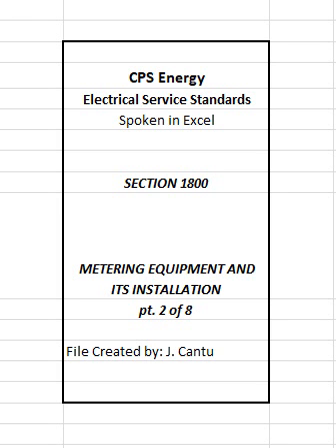Exception. Where customer's service design requires the use of a larger instrument transformer enclosure than those furnished by CPS Energy, customer shall submit to CPS Energy for approval an enclosure meeting CPS Energy's specifications and construction criteria. 2. Multiple meter installations. On multiple meter installations where CPS Energy instrument transformers are required in accordance with this section, a standard instrument transformer enclosure furnished by CPS Energy will be installed by customer on an auxiliary meter gutter. Exception. Code 12 enclosures are not permitted to be installed directly above an auxiliary gutter.